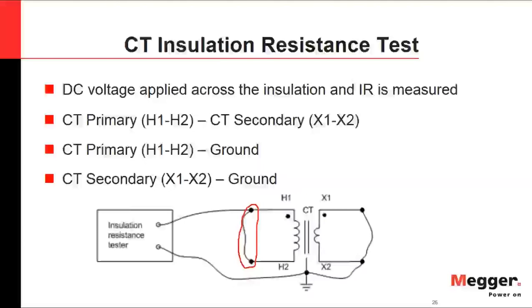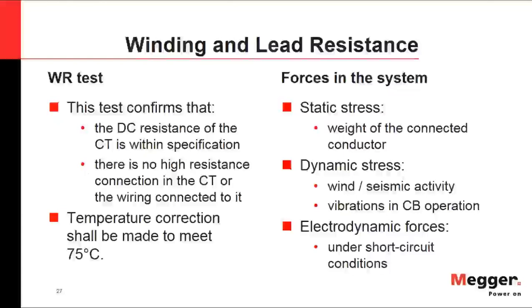For winding and lead resistance testing, we are trying to confirm that the DC resistance of the CT is within specification and that there are no high-resistance connections in the CT or its wiring. Temperature must be corrected to 75°C for comparability and trending analysis over time.